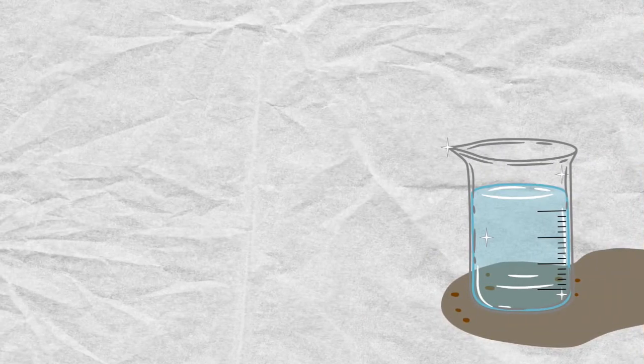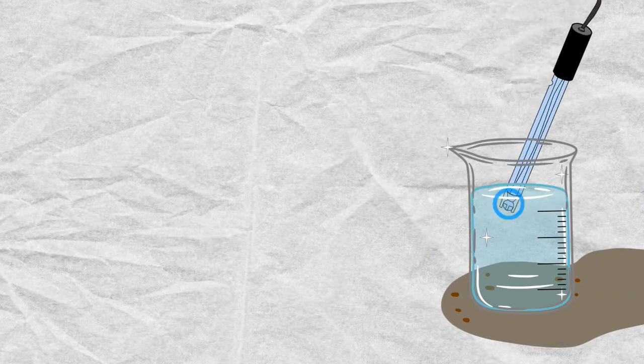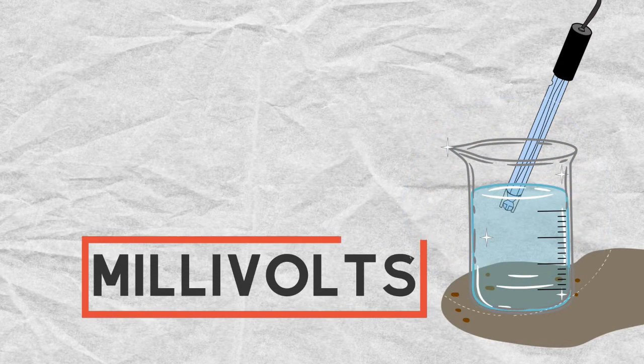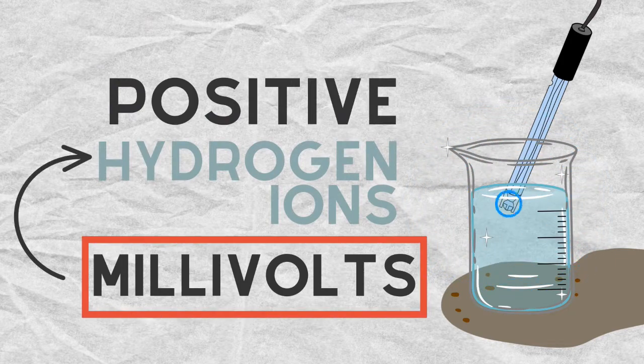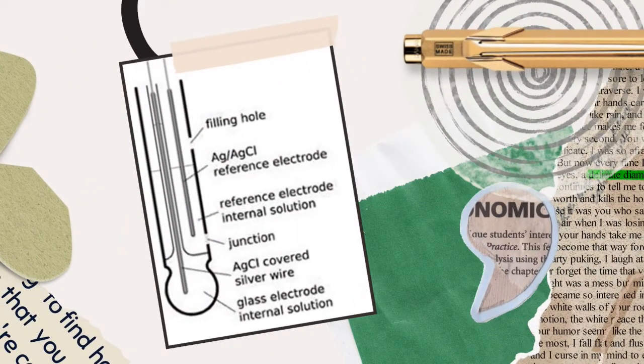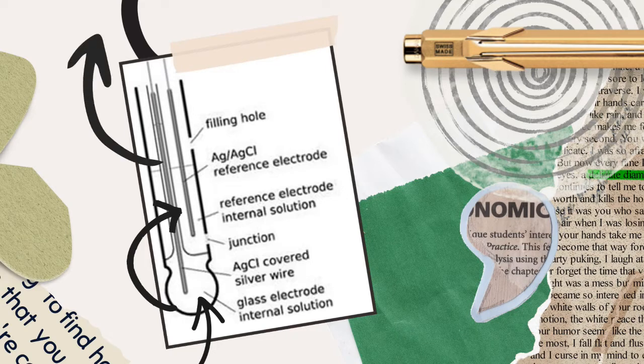As the electrode is immersed in the test solution, the glass bulb senses the hydrogen ions as a millivolt signal due to the positive charge of the hydrogen ions. The electrolyte or internal solution picks up the millivolt signal from the glass bulb. That signal is then passed to the internal electrode. The Ag/AgCl wire then passes that signal to the electrode cable that leads to the meter.